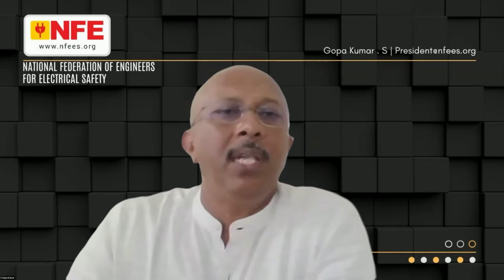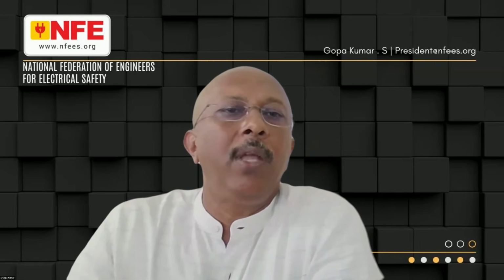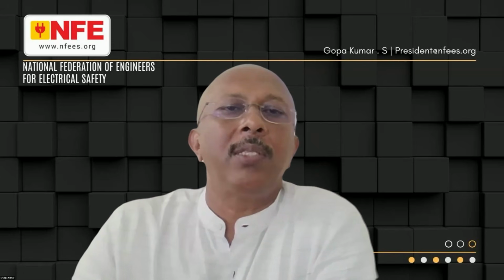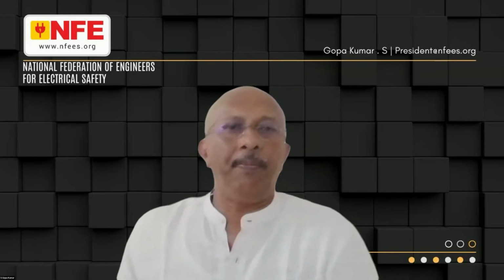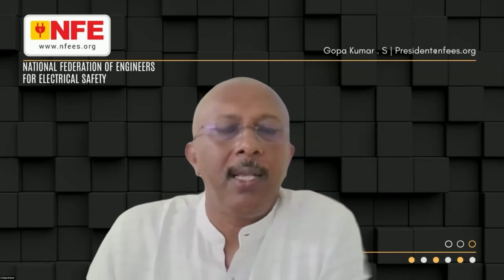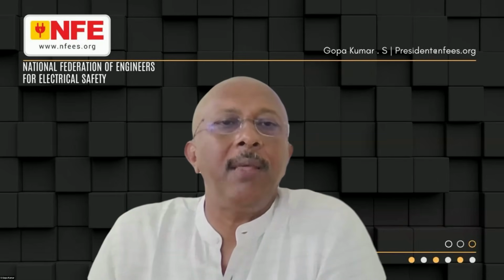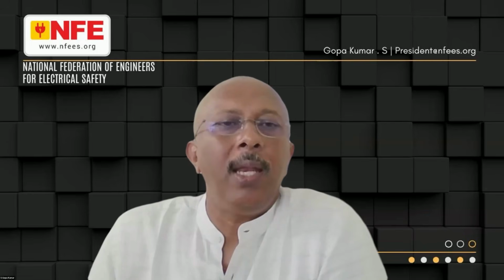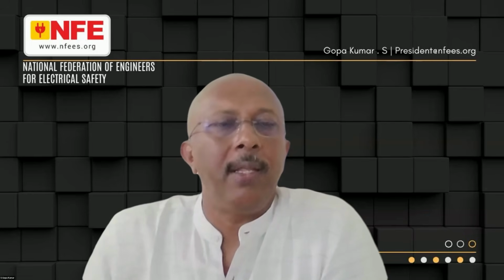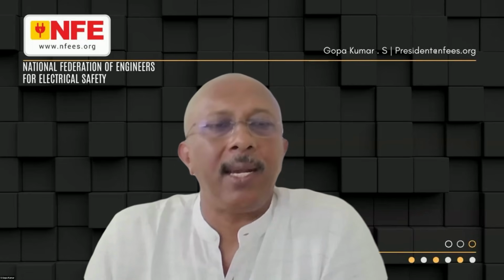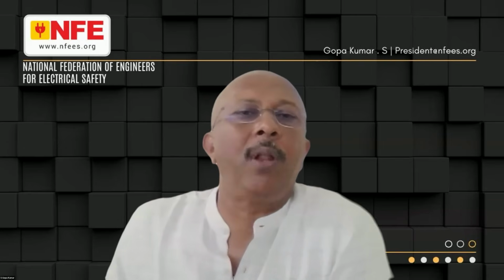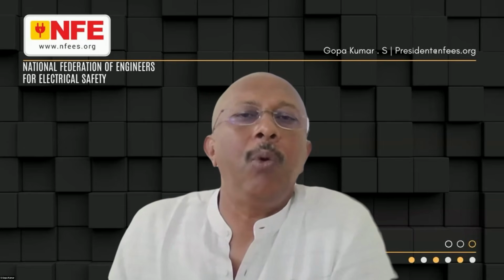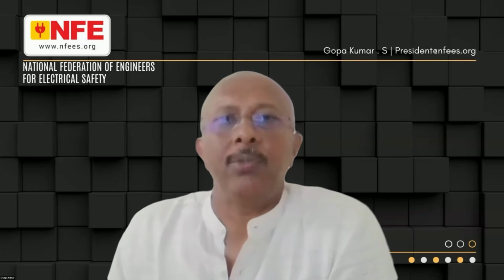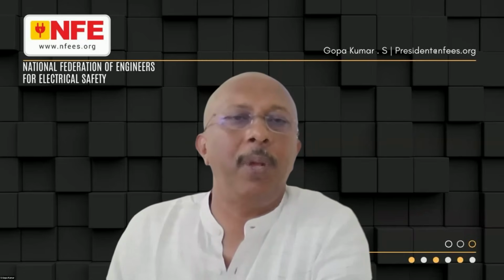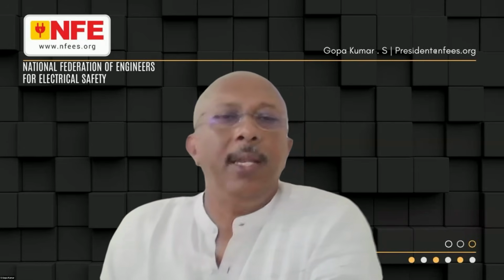Mr. Joshi is asking, if neutral and earth is short circuited in the internal wiring of the premise, or some local inverters may cause it, how to tackle this problem? Mr. Joshi, please understand that inside the installation, that means after the main distribution board, neutral and protective earth conductors must be separate. Neutral has to be treated as a phase conductor. The minimum insulation resistance between the neutral and the earth conductor must be 1 megaohm. So if you are violating that, of course, the chances of accidents will increase. So please treat neutral as a phase conductor, and it must be insulated.